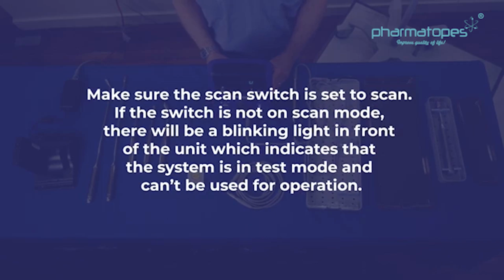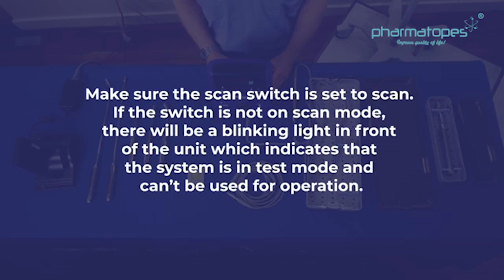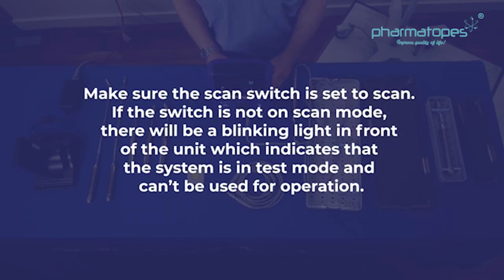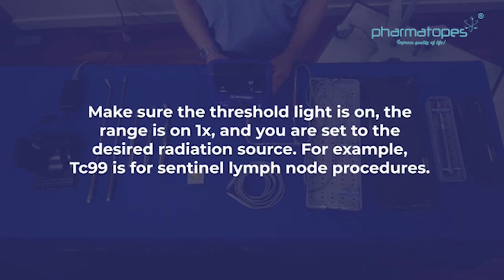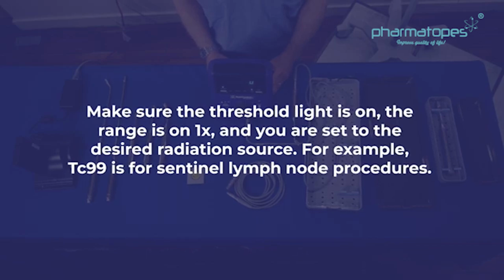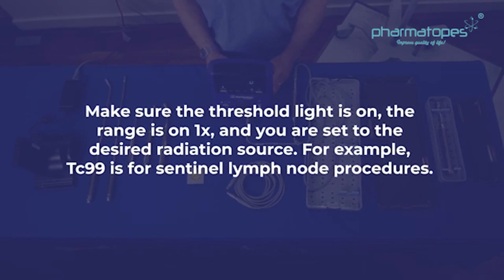Make sure the scan switch is set to scan. If the switch is not on scan mode, there will be a blinking light in front of the unit which indicates that the system is in test mode and can't be used for operation. Make sure the threshold light is on, the range is on 1x, and you are set to the desired radiation source. For example, technetium-99 is for sentinel lymph node procedures.